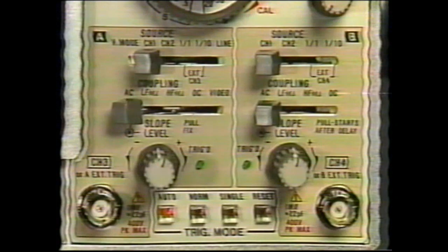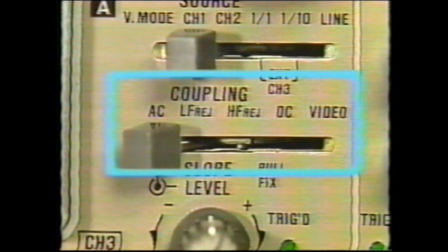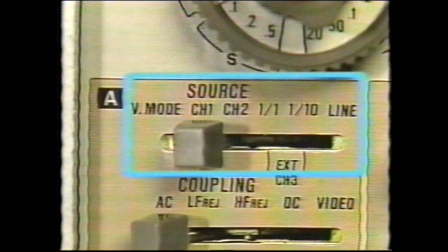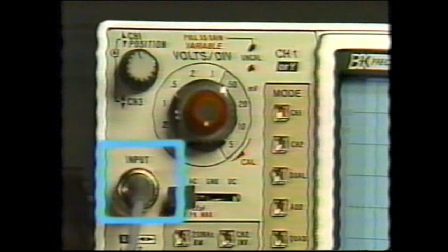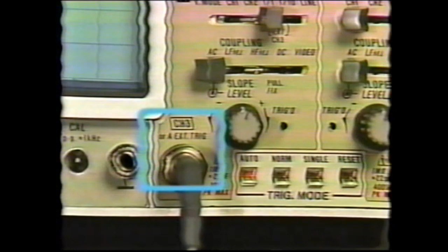The trigger section has quite a few associated terms and controls: source switch, coupling switch, slope and level controls, and trigger modes. The source switch determines where the source of the trigger signal will originate, either internally or externally. The internal position seeks an input signal from the vertical input jacks. The external position derives the input signal from an external trigger source.